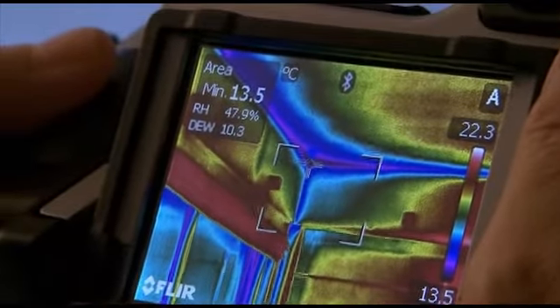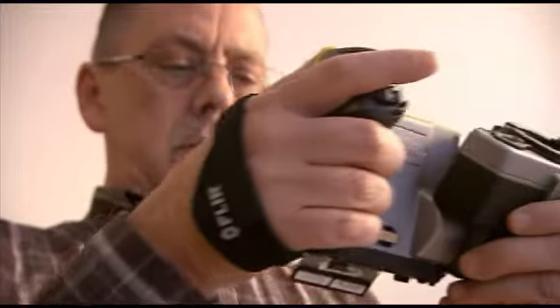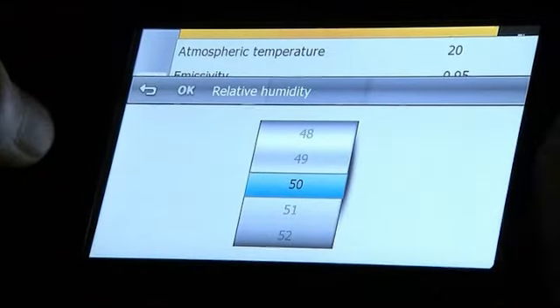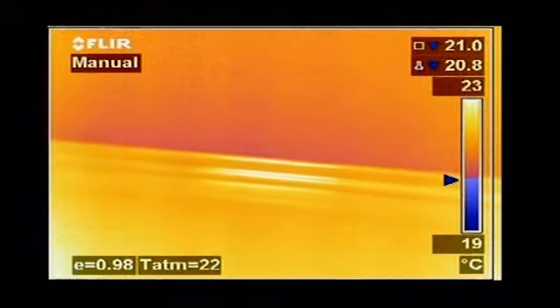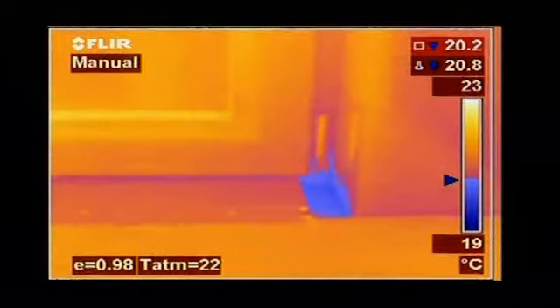If you don't have an Extech moisture meter to hand, all parameters used to identify potential condensation areas, such as relative humidity and temperature, can be set in the camera. The FLIR thermal imaging camera will calculate the dew point. Thermal imaging cameras with dew point visualisation software can highlight endangered locations automatically and provide a colour alarm in the image.